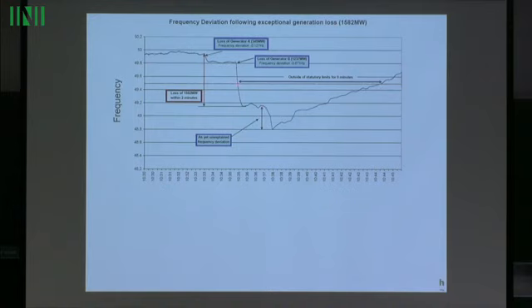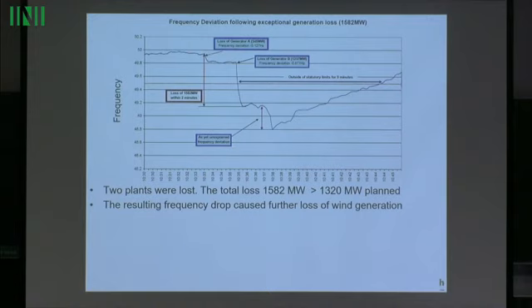but then it was stopped. The two plants dropped, so the total drop was 1582, which is more than 1320, which is planned. So actually it wouldn't be that bad, but because there was a huge drop of frequency following the huge loss, the frequency dropped to below 49, just about 49 hertz. We started to lose wind power plants.